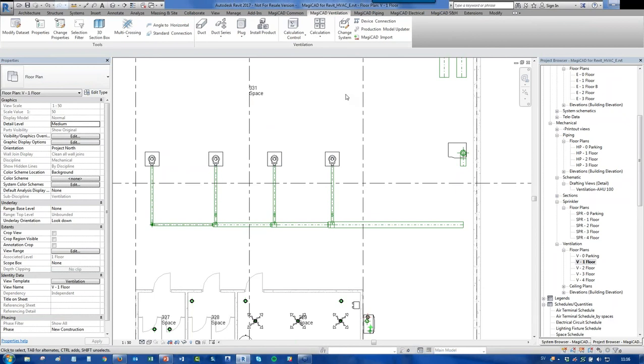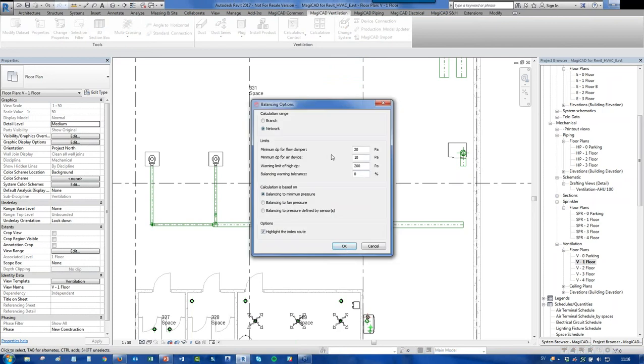So I want to do balancing now. How will it actually work if I try to balance? I now have built-in VCDs in those terminals, so there's some possibility for adjustments. I'm going for the balancing option, and then you have some choices, branch and network of course, but also minimum pressure drop for flow dampers and for air devices, and warning limits for high pressure drops, since we don't want to cause unnecessary energy or sound traps.